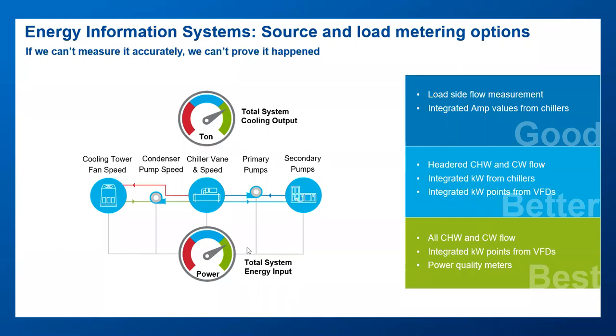And then, of course, the 'best' is measuring the energy inflows and outflows for all the equipment. So being able to measure not just electric power, but chilled water flow, condenser water flow to each device, and measuring that electricity with utility grade submeters, at least on the largest, highest power consumers with high power quality meters.